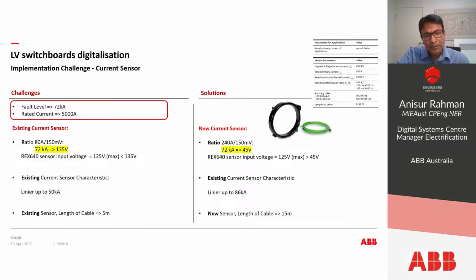And that's why we needed to develop a new sensor, and our ABB Czech factory developed a new sensor for LV application with a greater ratio, which is 240A:150mV, and it gives us linearity up to 86 kA.